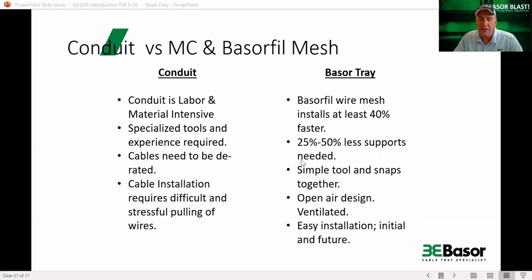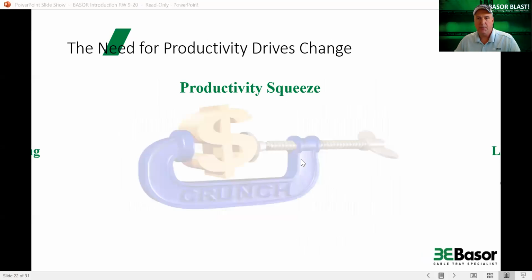But if you use our wire mesh, it installs at least 40% faster, sometimes greater. You need 25 to 50% fewer supports, and you can make a larger span. It's simple to put together with simple tools—it snaps together, you just bend and crimp. You don't need a lot of nuts and bolts, a tugger, or a bender—things that are costly and difficult to use. It's an open air design, ventilated, and very easy to install for future applications, so you don't need a new structure when making an add or change.